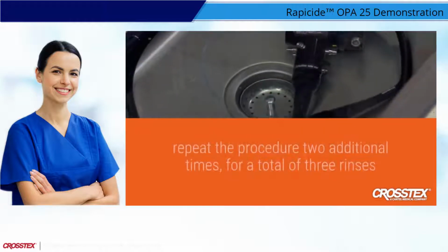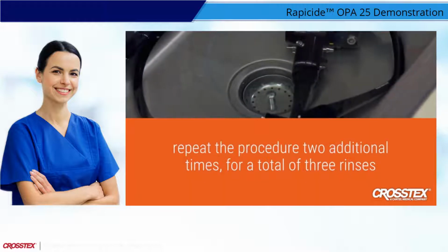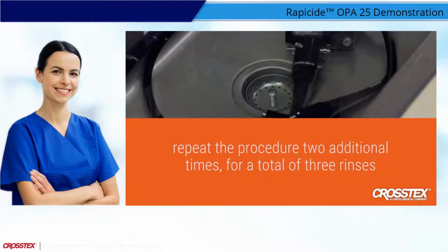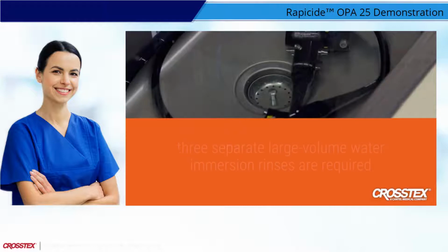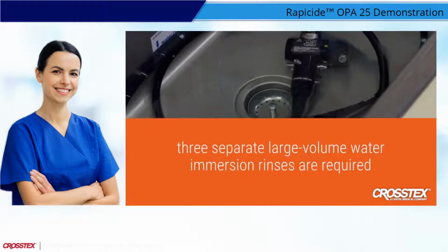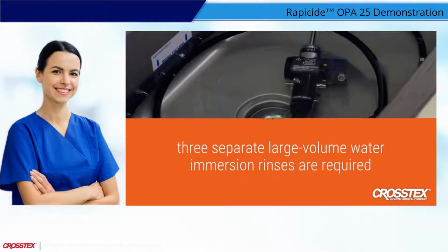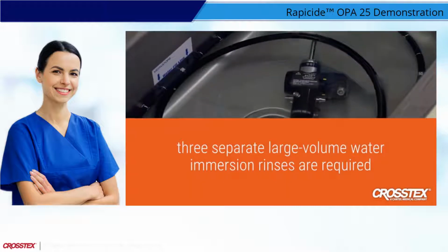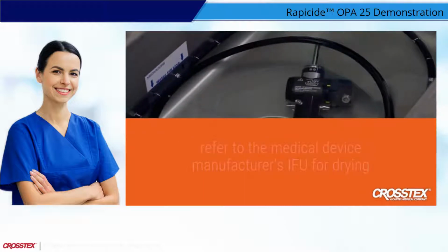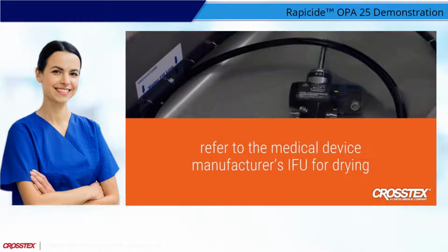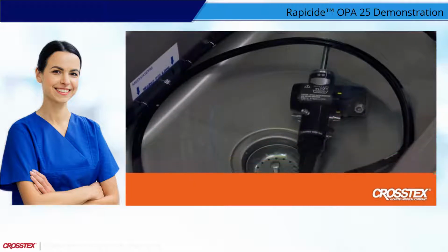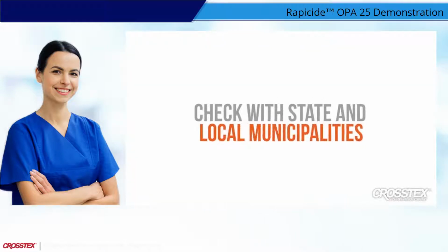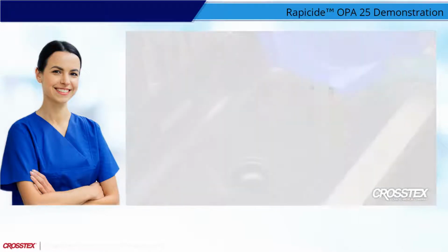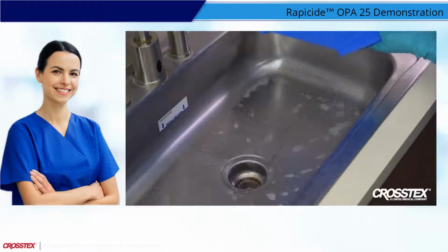Repeat the procedure 2 additional times for a total of 3 rinses with large volumes of fresh water to remove any residue. 3 separate large volume water immersion rinses are required unless otherwise specified by the device manufacturer's instructions. Refer to the medical device manufacturer's IFU for drying. Be sure to follow any state, local, or department disposal regulations when disposing of Rapicide HLD, unless otherwise specified.